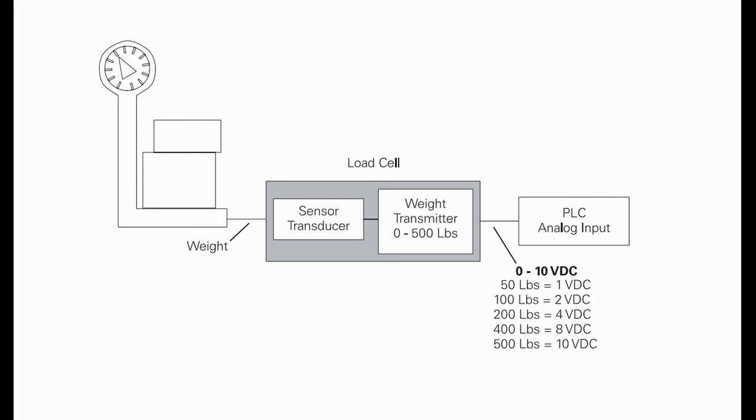In this example, the load cell is converting a value of weight into a 0 to 10 V DC output. The output value depends entirely on the manufacturer specifications for the device. This load cell outputs 0 to 10 V DC for a 0 to 500 pounds input.